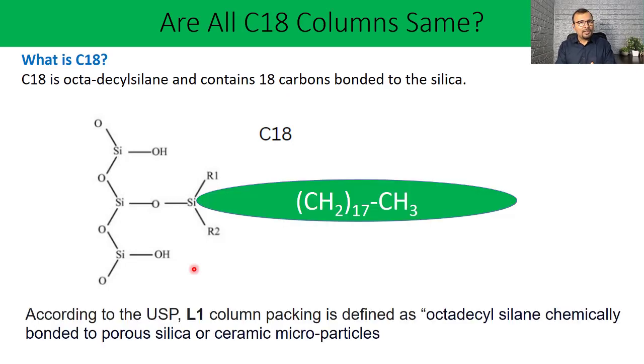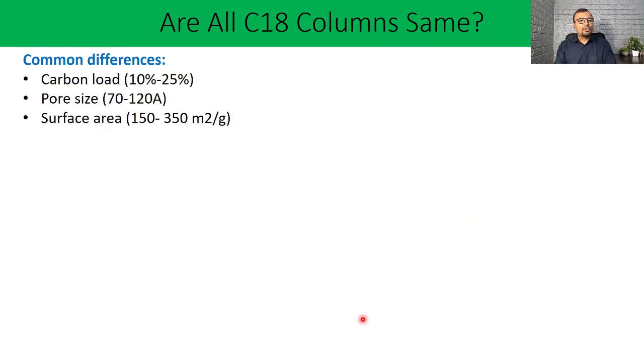According to the USP, the C18 stationary phase is classified as the L1 column packing, and there is no further distinguishing between different C18 stationary phases. The common differences based on dimension are obvious, like different length, diameter, particle size will certainly have different chromatographic impact. But there are certain important factors which are also different from one column to another column, like carbon load, pore size, and surface area.